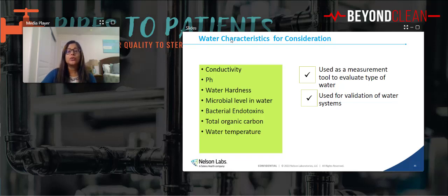Absolutely. We measure microbial levels every week across all five of our different buildings. We measure pH, bacterial endotoxins, and TOC every month, and conductivity and water hardness depending on the season, though it's due yearly we may do it intermittently. So yes, we do have a quality system for water monitoring, to ensure the water we're using for processing and other tests meets what's required by standards.